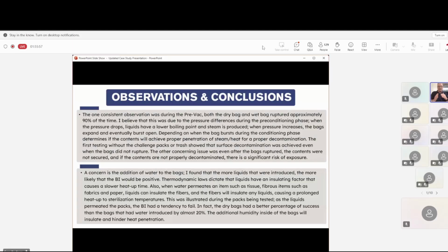Because of the pressure differences, when that pressure is going in and vacuuming out, eventually that bag is going to try to bust open. And so the problem is, where in a preconditioning does it bust open? If it busts open in 3 or 4, you're treating it just like a gravity, and you're not going to get that penetration inside. And remember, folks, this is only 5% trash that I put in it. You're seeing how little it is. Imagine if that bag is full, and the more you put in it, the more challenges that you have.